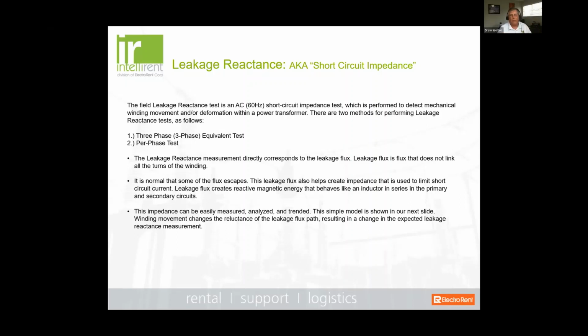Well, consider this: if you have physical damage to that trough, or somebody takes a rock and throws it in the middle, you're going to get a higher resistance. Okay, you're going to have more leakage. Well, leakage flux is kind of like the same thing, and that's what we're looking at. So it is normal that some flux escapes. And this leakage flux also helps create an impedance that is used to limit short circuit current. Leakage flux creates a reactive magnetic energy that behaves like an inductor in series in the primary and secondary circuits.